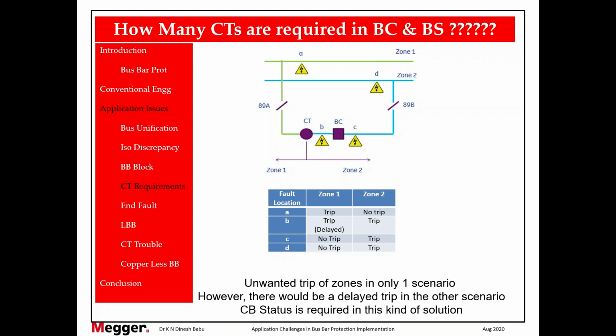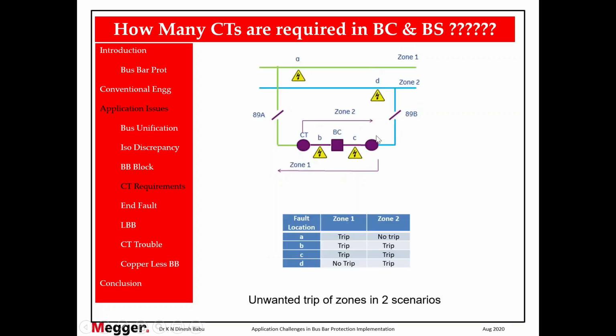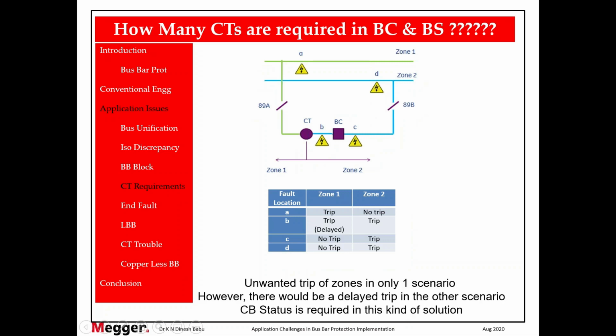So what is the conclusion? We are not telling you to use 2 CTs or to use a single CT. We should know the pros and cons of both, because in the previous method we are spending so much money installing another CT and we are actually creating unwanted trips in 2 scenarios. Whereas here, at reduced cost, you are getting a better solution, with only one scenario. However, we cannot call this a better solution because there is a delayed tripping. Now this is left to the user to decide, because for distance protection in the relay specification we mention that a 40 millisecond delay is acceptable. And if you have only 1 or 2 feeders and it is a transfer bus coupler, then why should we go for such a costly, expensive solution by adding another CT and creating 2 scenarios against the power system protection principle?